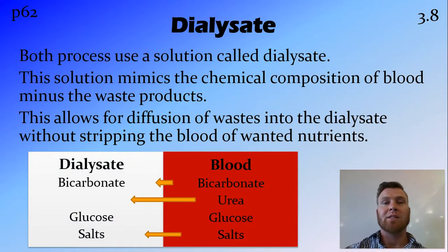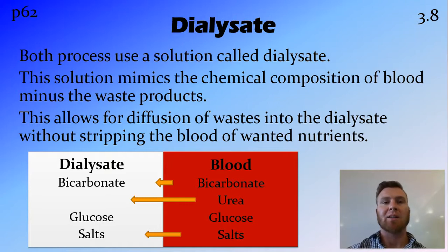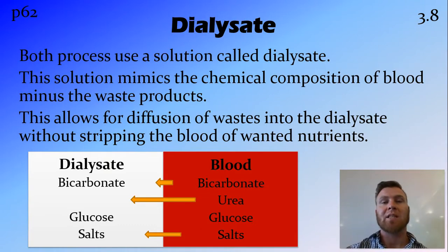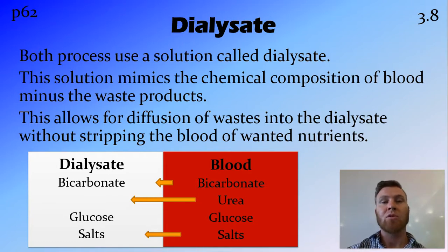Both these processes use a liquid called dialysate, and this liquid mimics the chemical composition of the blood but doesn't have those waste products in it. So if the blood has a certain amount of glucose in it, the dialysate will have around the same amount of sugar the blood is supposed to have. It will have the same amount of salts such as sodium chloride that the blood is supposed to have, and this allows for diffusion of those things they don't want in the blood. For example, urea — because there's no urea in the dialysate — very quickly and easily diffuses across that semi-permeable membrane. Glucose on the other hand is found on both sides of the semi-permeable membrane, so there's going to be no net movement unless the levels in the blood are somewhat out.